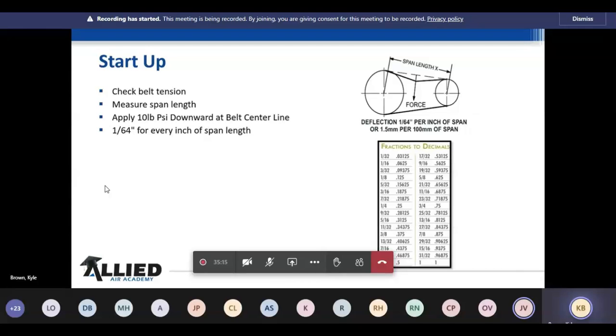Now the instructions are going to tell you go back 24 to 48 hours. I understand that's not feasible for everybody. But if there are multiple units on the rooftop and they're going to be there multiple days, I would at least instruct the mechanical contractors, the technicians, say, hey, if you're going to be up there, go ahead and check these out once again after they've had some runtime on it, if you get the opportunity. If you don't, make sure you understand that that belt may loosen up.